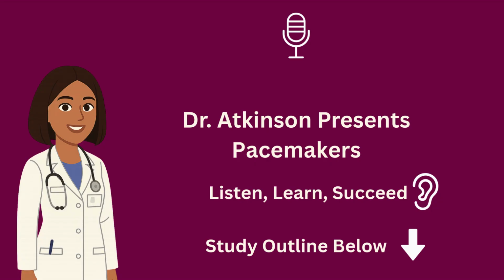Ongoing surveillance of pacemaker function is essential. Today, most devices include remote monitoring systems, which have replaced many routine in-person visits and are linked to better survival. There are several types: trans-telephonic systems using a landline phone, inductive systems using a wand with either landline or cellular transmission, and wandless systems that communicate by radio frequency. Remote monitoring provides the cardiologist with ECG data, pacing rates, generator settings, battery life, sensing function, lead integrity, and the number of pacing events. This allows early identification of problems, reassurance for patients, and timely interventions, even if the patient lives far from a cardiology clinic.